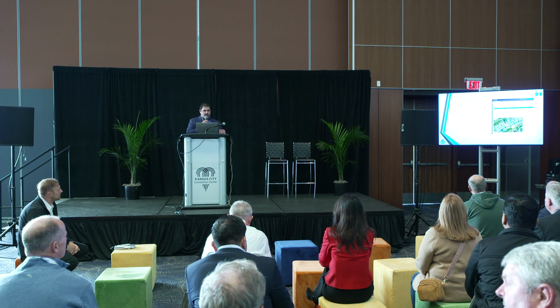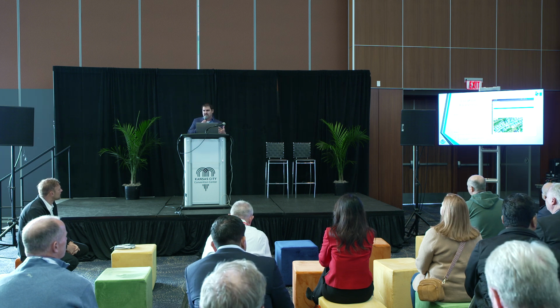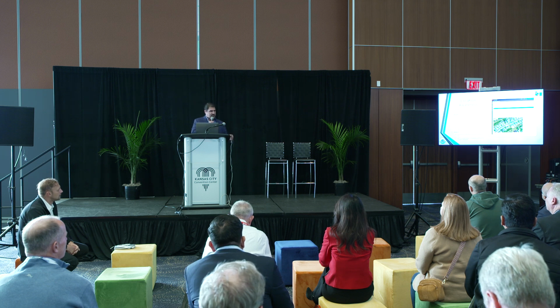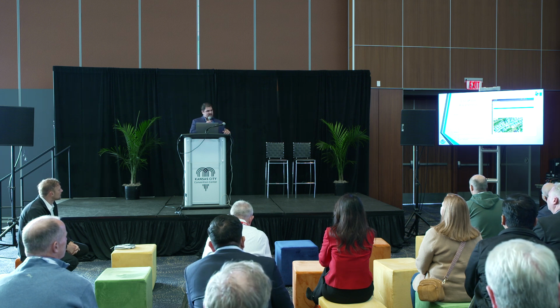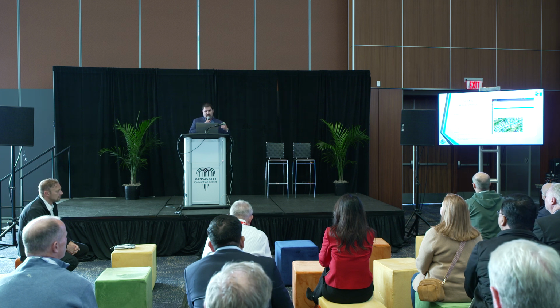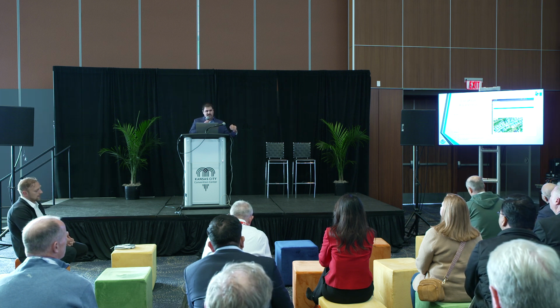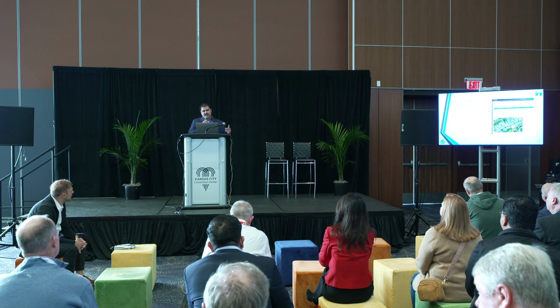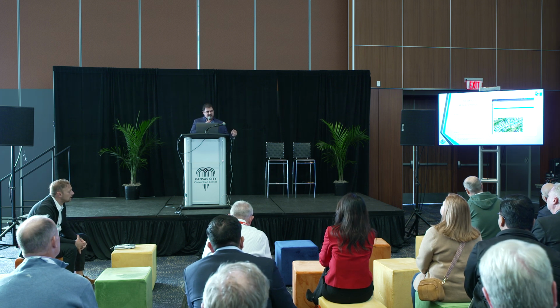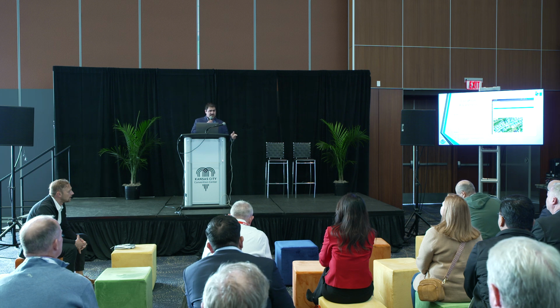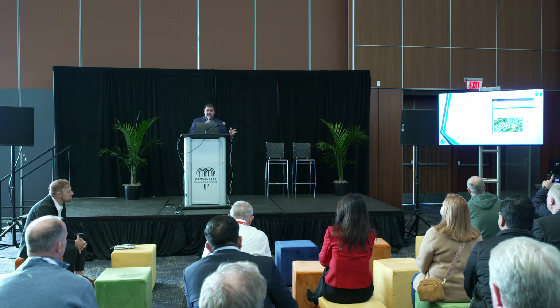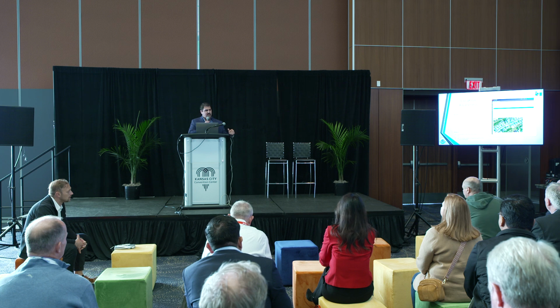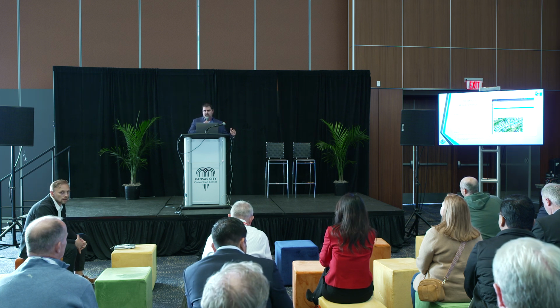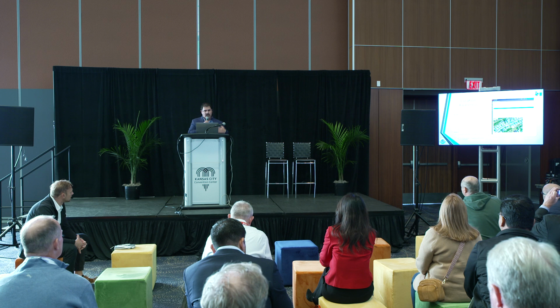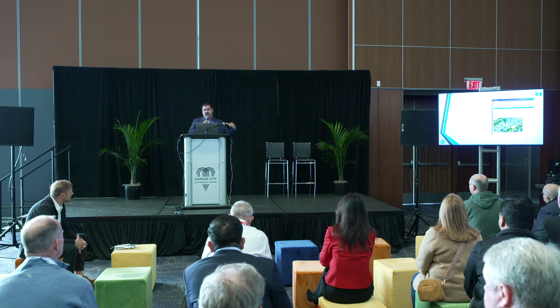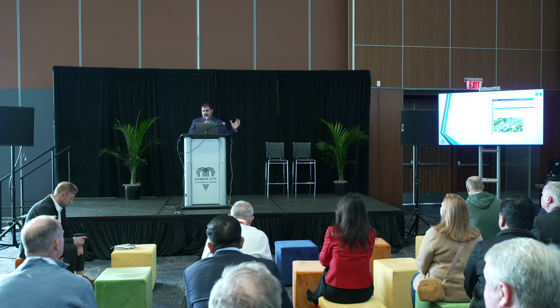This new technology also has the ability to sample sub-second — 2, 4, and 32 kilohertz. So when we see the sine wave and the zero crossing, we can take a snapshot of that moment and understand, relative to our peers electrically, what our electrical contribution from a phase perspective is. So now I know how I am electrically connected to the transformer, and what my phase contribution to the transformer is. Because I'm tracking each individual waveform anomaly over time, I can look at those signatures and distortions of the voltage and current waveforms relative to each other, and also assign which asset — from a substation, transformer, or feeder perspective — I belong to.